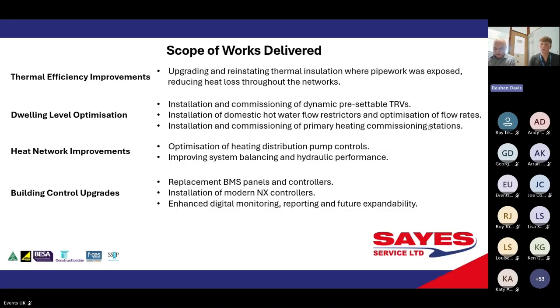Within the individual dwellings, we delivered a series of optimisation measures, including the installation and commissioning of dynamic presettable TRVs, domestic hot water flow restrictors, and primary heating commissioning stations. Alongside this, we reviewed and optimised pump controls to improve the hydraulic performance and system balancing throughout the buildings.